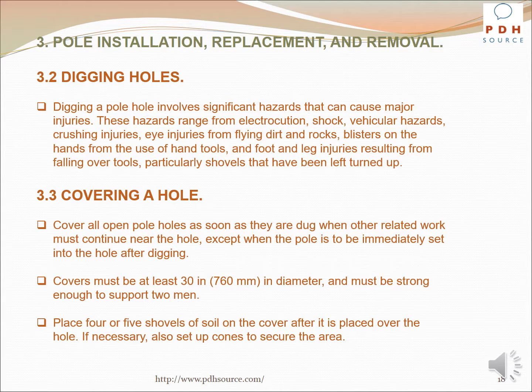Cover all open pole holes as soon as they are dug when other related work must continue near the hole, except when the pole is to be immediately set into the hole after digging. Covers must be at least 30 inches in diameter and must be strong enough to support 2 men. Place 4 or 5 shovels of soil on the cover after it is placed over the hole. If necessary, also set up cones to secure the area.